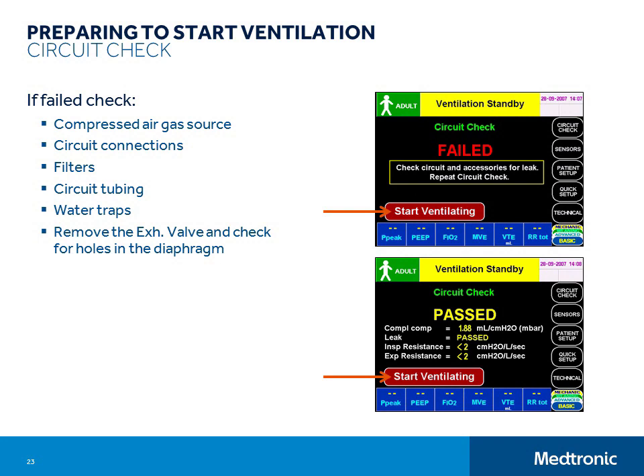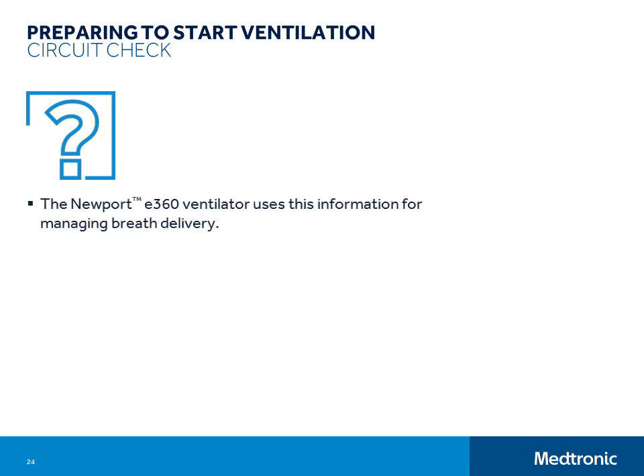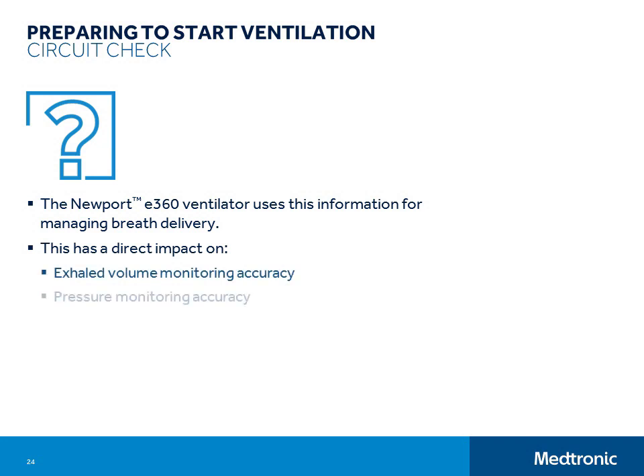Some people are tempted to skip the circuit check, even though the e360 circuit check is very short and easy to do. So why do it? Well, the ventilator gathers important information and performs important calibrations during the circuit check. The information is used to manage breath delivery, and the calibrations ensure accurate measurements and servo controlling. The circuit check has a direct impact on volume monitoring accuracy, pressure monitoring accuracy, pressure management accuracy, and the ability to compensate for compressible volume in the breathing circuit.